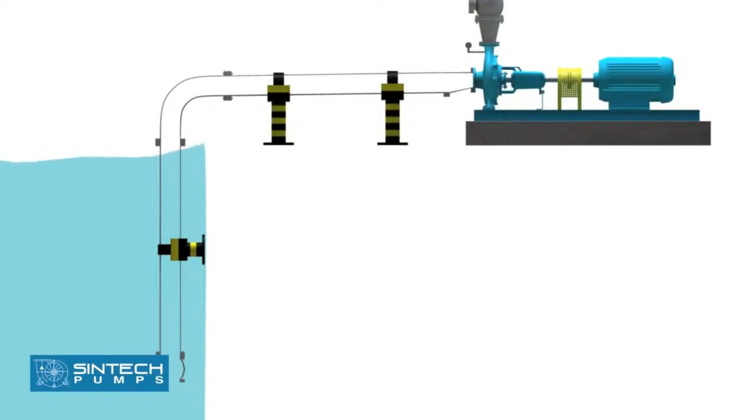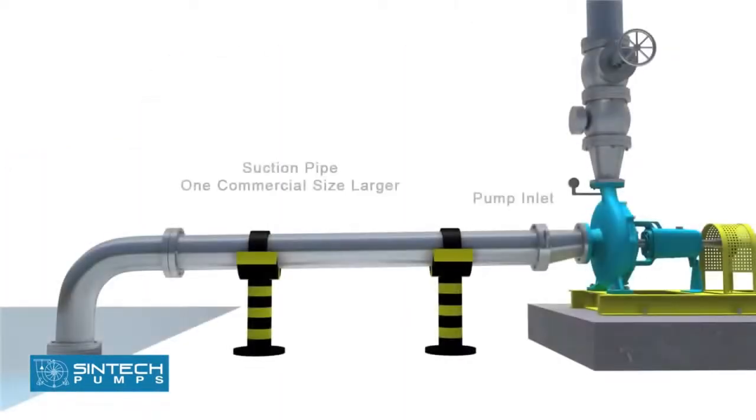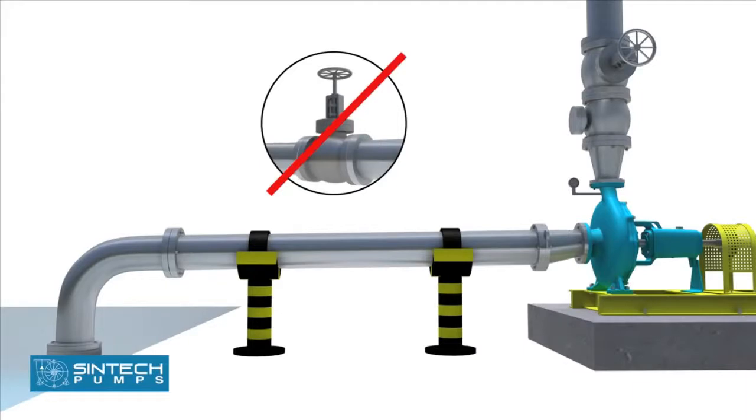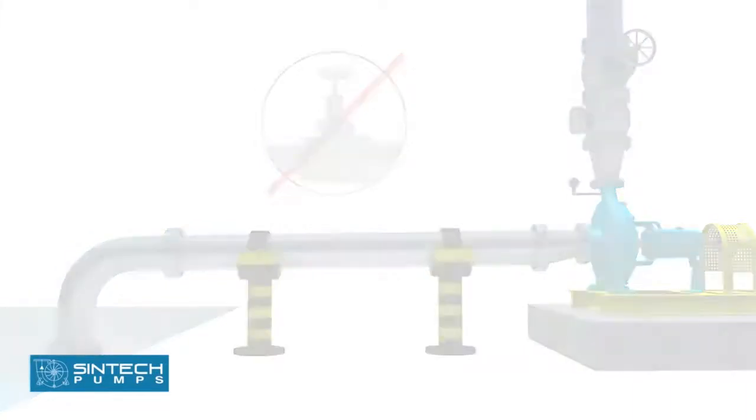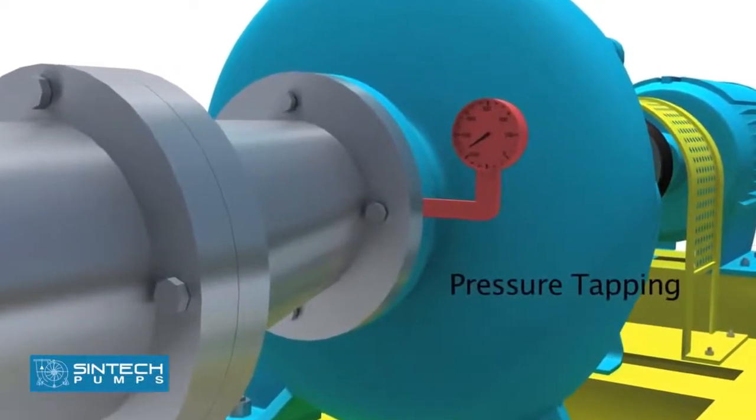The suction pipe should be sized to ensure the liquid velocity of not more than 2 meters per second. The suction pipe size should be at least one commercial size larger than the opening of the pump inlet. All suction pipes should have a continuous rise to the pump suction inlet. 6 millimeter per 100 millimeter slope is recommended. No isolation valve is recommended. There should be a tapping provided for installing a vacuum gauge in suction line.